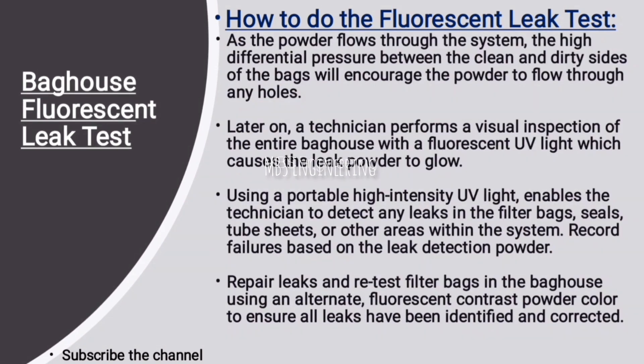After the injection of the fluorescent powder, as the powder flows through the system, the high differential pressure between the clean and dirty sides of the bags will encourage the powder to flow through any holes. A technician then performs a visual inspection of the entire bag house with a fluorescent UV light, which causes the leak powder to glow. Using a portable high intensity UV light enables the technician to detect any leaks in the filter bags, seals, tube sheets, or other areas within the system. Record failures based on the leak detection powder.